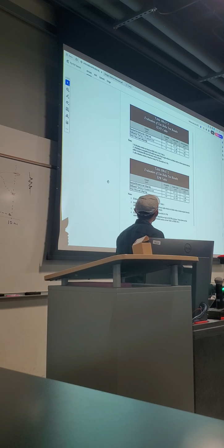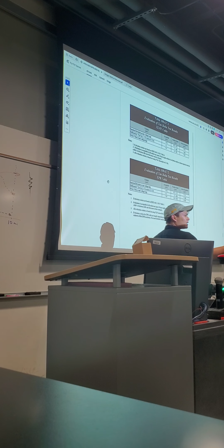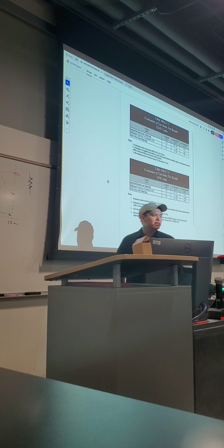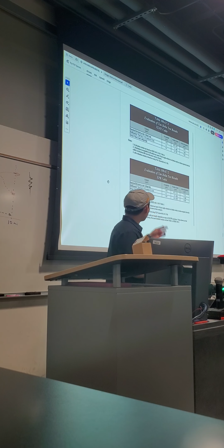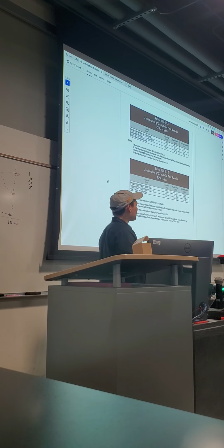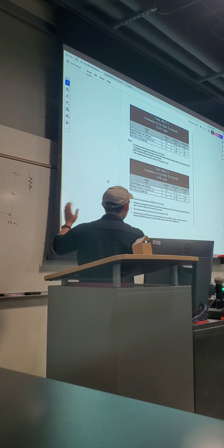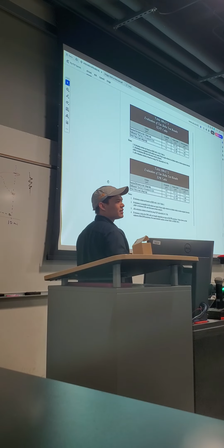this is the one we're going to follow to tell our customer exactly what we found, like we told them when we just looked at the dielectric absorption and said good, dangerous, whatever. We're going to say acceptable, further study, or action required. We know how the NETA MTS tables work, and if we can find the correct column that our numbers fall into, we'll be able to determine pass or fail. And then write that up in a comprehensive manner to our customer. We're going to have the data to support that, and that is exactly how we pay the bill.